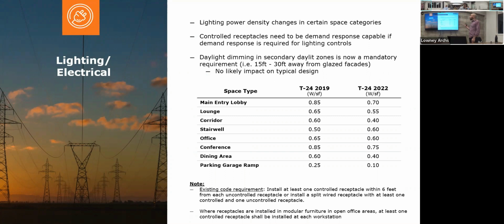The code already had a requirement on receptacles: for all new buildings, a certain number of receptacles would need to be automatically controlled. And now if you have that, they also need to be demand response capable.